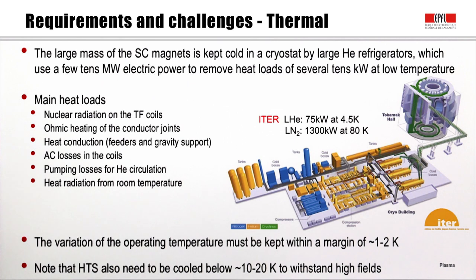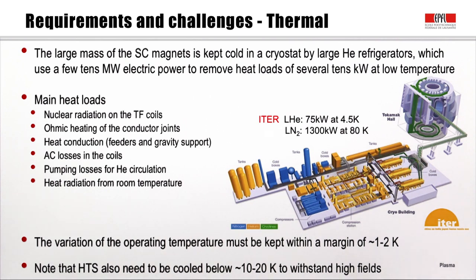The main heat loads are: nuclear radiation on the TF coils from neutrons generated by fusion reactions in the plasma core; ohmic heating at conductor joints; heat conduction through feeders and gravity supports; AC losses in the coils; pumping losses for helium circulation; and heat radiation from room-temperature components. The operating temperature variation must be kept within a margin of 1, maximum 2, degrees Kelvin. Even for high-temperature superconductors, cooling below 10 to 20 K is needed to withstand high fields and achieve good current densities.